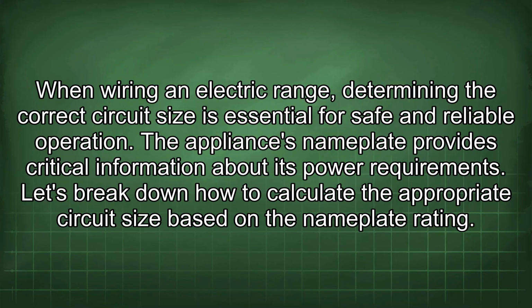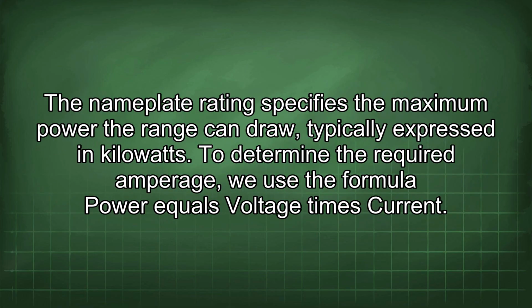When wiring an electric range, determining the correct circuit size is essential for safe and reliable operation. The appliance's nameplate provides critical information about its power requirements. Let's break down how to calculate the appropriate circuit size based on the nameplate rating. The nameplate rating specifies the maximum power the range can draw, typically expressed in kilowatts.